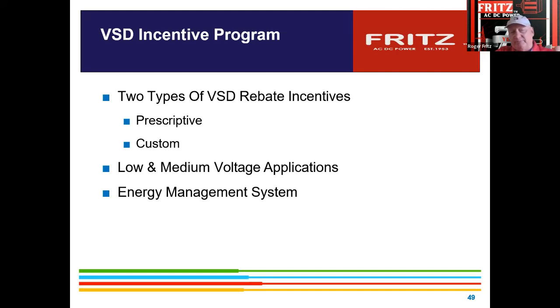There's low voltage, up to 480, 575 volt. They consider the 200 to 575 volt all low voltage rated. We also do medium voltage controls that go from 2300 volt clear up to 13K if you need, because they do build inverters that actually build power. They transmit power DC and then put inverters on the back end side. But the majority of what we deal with is medium voltage, which is 4160 volt motors in America. Sometimes there's 6,000 volt overseas.